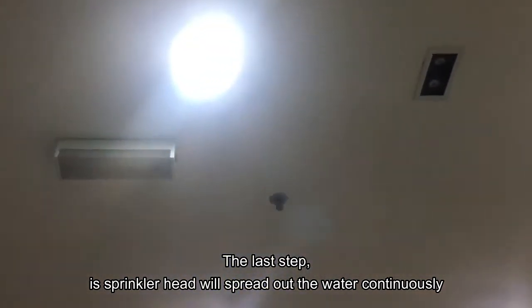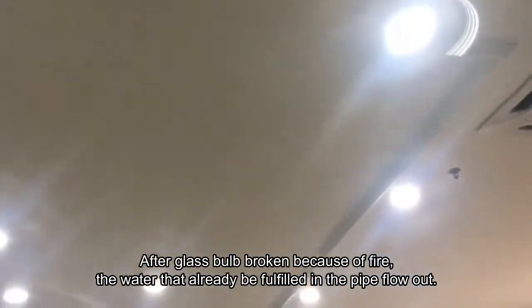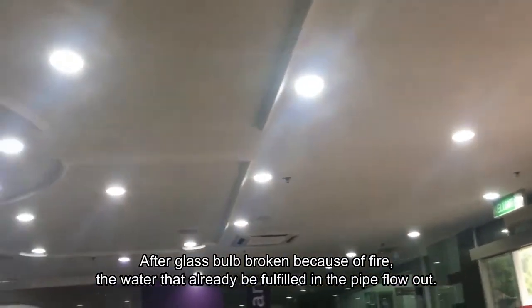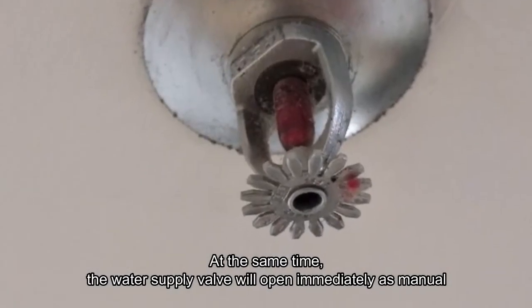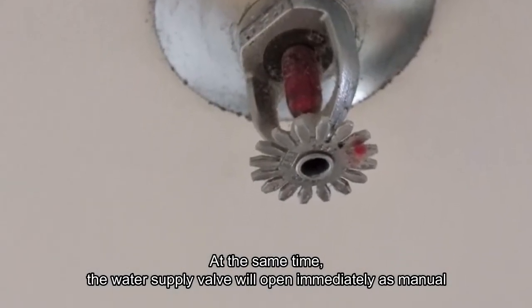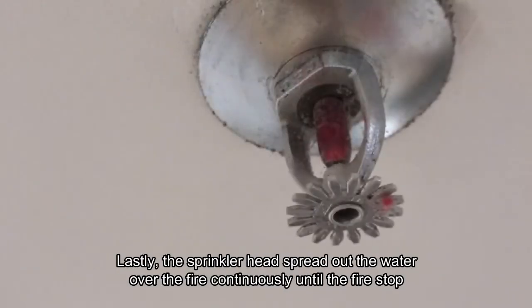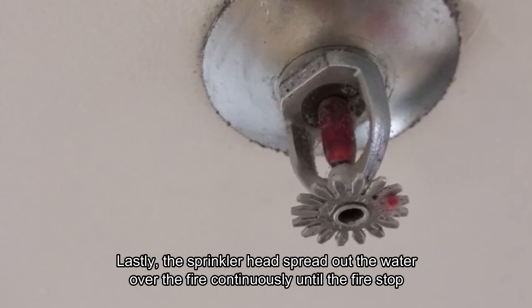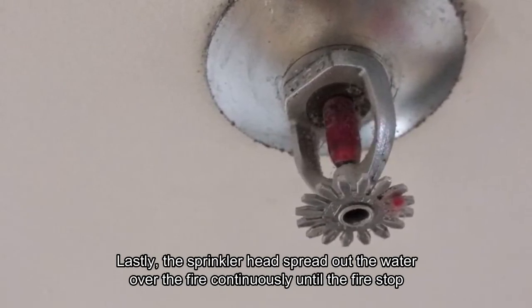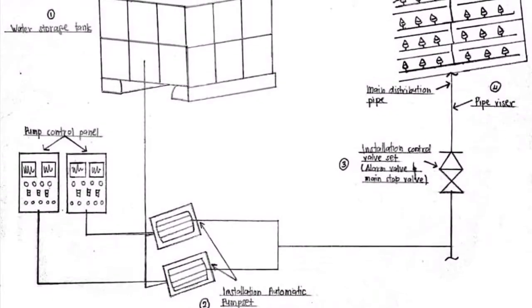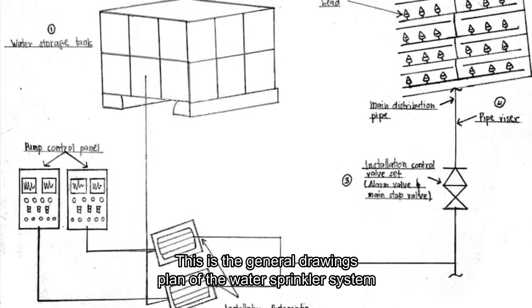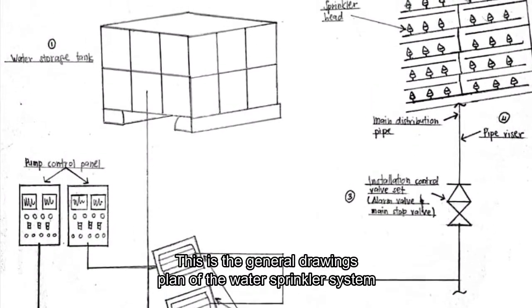The last step is that the sprinkler head will spray out the water continuously. After the glass bulb breaks because of fire, the water already filled in the pipe will flow out. At the same time, the water supply valve opens immediately, as manual. Lastly, the sprinkler heads can spray water over the fire continuously until the fire stops. This is a general drawing plan of the water sprinkler system.